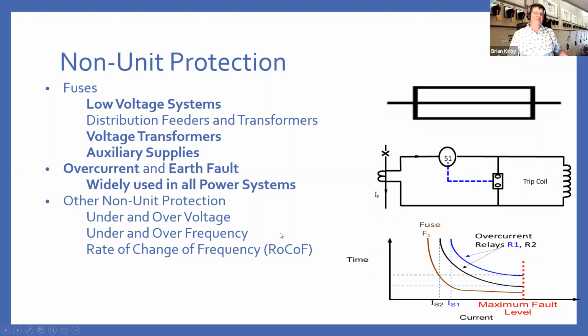There are other non-unit protection doing voltage and frequency and rate of change of frequency, but they are not as commonly used. They are used, but not as commonly, because they tend to be very specific to the application. Whereas overcurrent and earth fault are pretty much used everywhere. This diagram here shows for a particular level of fault, the different discrimination. I'll come into more detail on that on another slide. I'll show how that curve is derived.